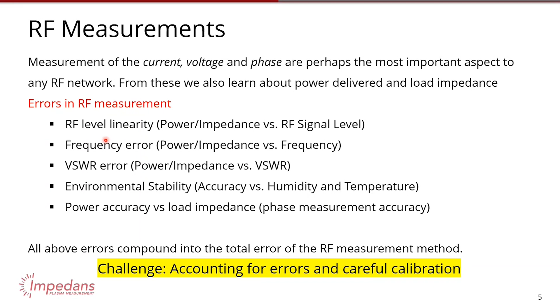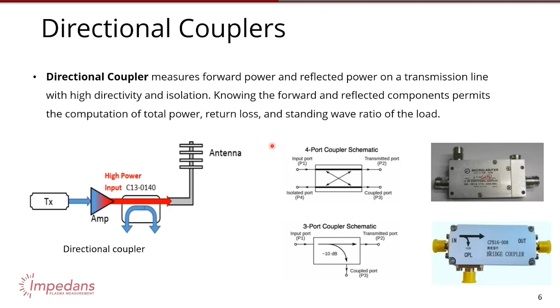Put simply, a directional coupler measures forward and reflected power on a transmission line, and it has high directivity and isolation. So if you know the forward power and reflected power, it means you know the total power, the return loss, and you'll know the standing wave ratio of the load. So this is a very old technology, quite simple, but has a couple of drawbacks. Usually power measurements are only accurate over a limited impedance range or a limited VSWR range. The accuracy tends to be impacted by temperature and humidity. All this can be compensated for, and they can have complex designs, especially for high voltage applications.